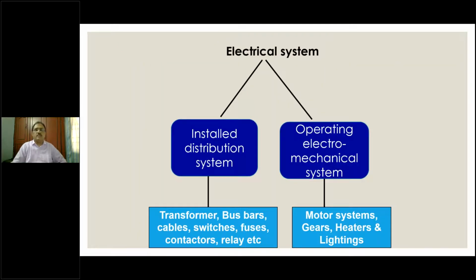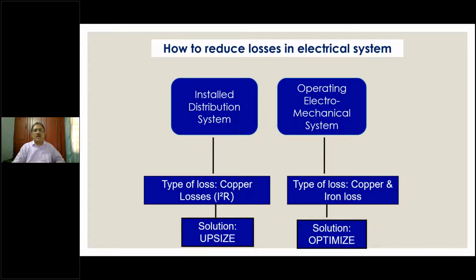So how do we broadly look at the opportunity available for saving? The installed distribution system, like I already said, comprises transformer, bus bar, cable, switches, fuses, contactors, relays, capacitors, and so on. Even UPS is a part of the installed distribution system. The operating electromechanical system is largely motors, gears, heaters, and lighting, and some IT loads also. Now, what are the choices available for energy saving broadly? In the installed system, the losses are I square R losses, or copper losses. Now, we can't change the profile of I.